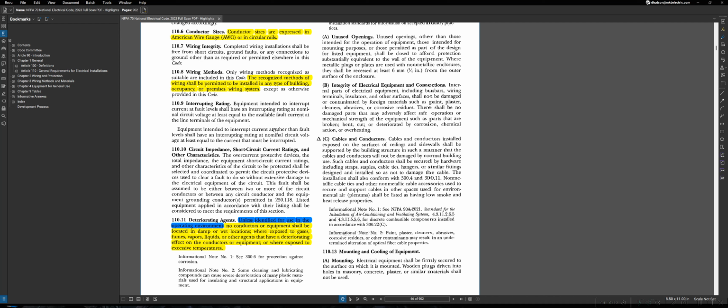On that same note, the NEC will not recognize wiring methods that are limited to a specific installation. One of the most common examples of this is URD cable, which you may see at a big box store, underground residential distribution cabling. That specific type of cabling isn't recognized by the NEC, since the manufacturer only allows it to be installed in residential applications.